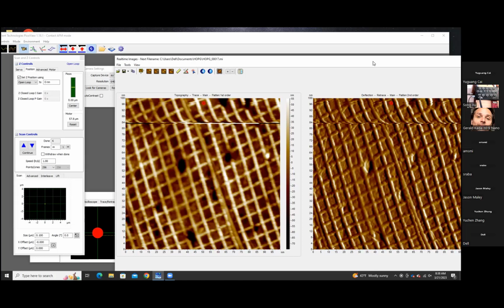And the reason why relative is important is because the reason that you're getting any voltage whatsoever has everything to do with your scanner calibration file. So if you change your scanner calibration file, those values will change. So don't stress, just know that you're centered in the power supply range. These power supplies go from 220 volts DC to negative 220 volts DC. So 3 volts is not something I would consider an issue at this point. We need to take more measurements.